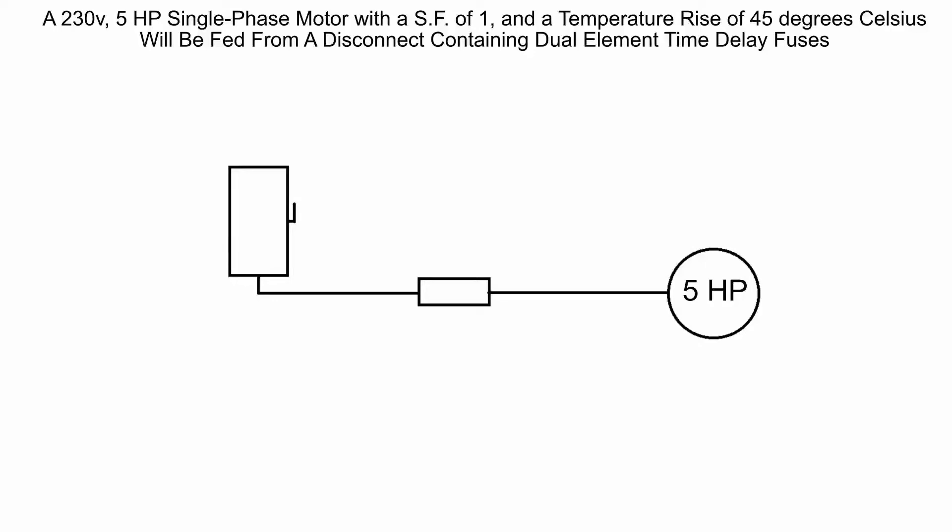In this video we're going to be learning how to size a single phase motor along with its thermal overloads, branch circuit conductors, and its overcurrent protective device. In the question we have, it says a 230 volt, 5 horsepower single phase motor with a service factor of 1 and a temperature rise of 45 degrees Celsius will be fed from a disconnect containing dual element time delay fuses.